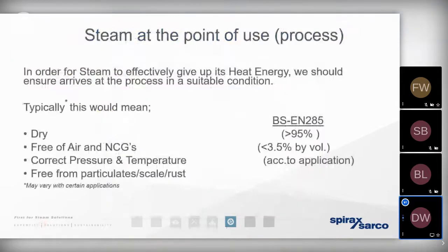As we've mentioned, one of the most important things to bear in mind is we want to ensure that the steam is kept as dry as we possibly can and free of air and other non-condensable gases. And BS EN 285 is a standard that we can use to benchmark the condition or the quality of the steam. We'll come on and speak about this in a little bit more detail in coming weeks. It is a standard that is widely referenced by applications that may use steam for critical purposes, such as hospitals, pharmaceutical, food and beverage, fine chemical applications.